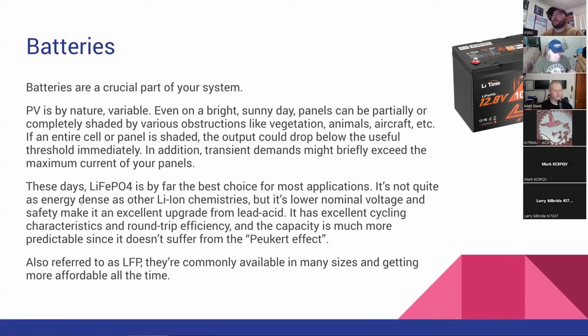The other problem with lead acid is they have the Peukert effect, named after Peukert, which effectively means that as you increase the load on them, their effective capacity decreases. So if you have a 100 amp hour lead acid battery and you're drawing it down in an hour or two - so you're pulling a 1C or 2C rate on it - you're going to be effectively using a 50 amp hour battery. That's just how it works.